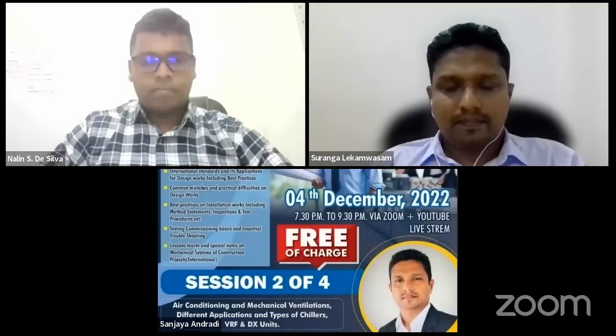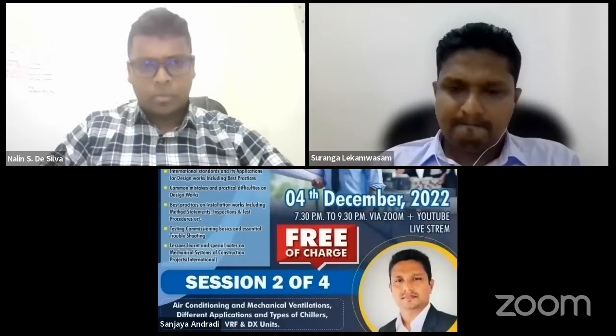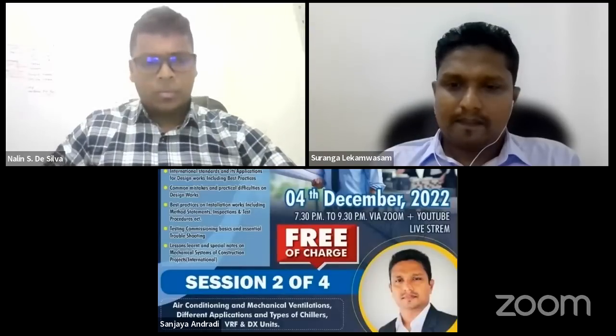Yeah, so I'm working in an apparel sector, and in our factory we are using magnetic bearing chillers. My question is, we are using it for around 7 years, but the main issue is we are operating it with the PFR relays. So when there is a power failure or power imbalance, the system will go totally down, and then we need to restart. And this system is normally synchronized with the BMS system also. So what are the things we can do to minimize this issue?